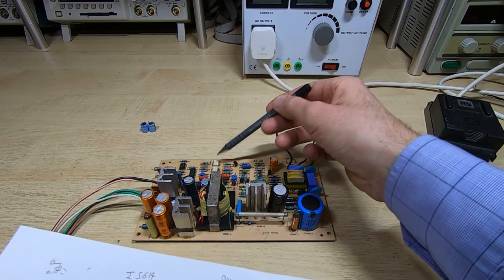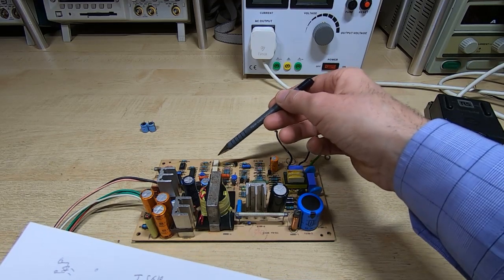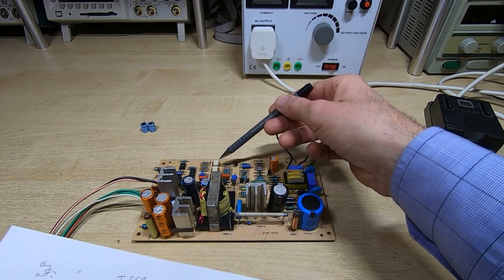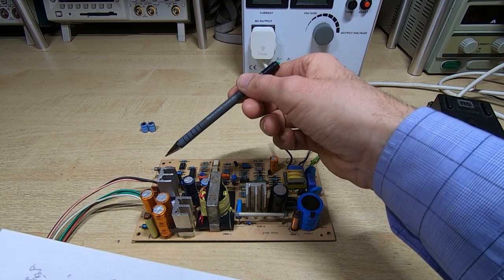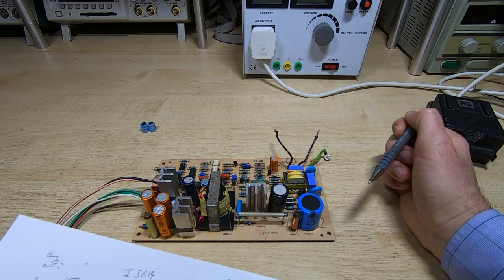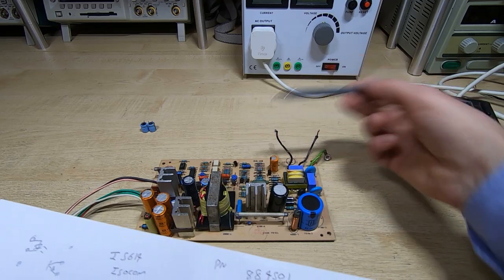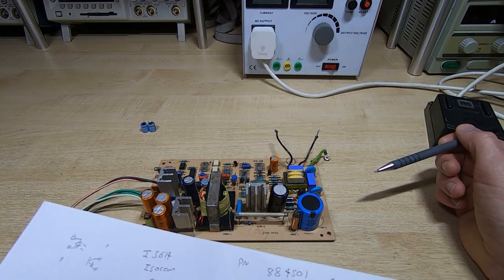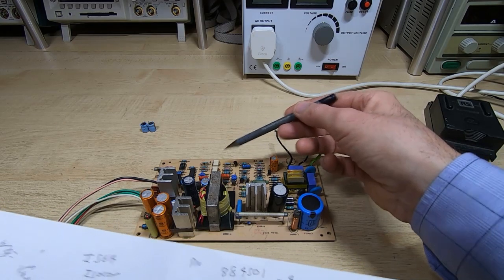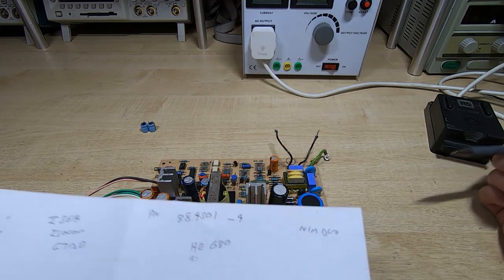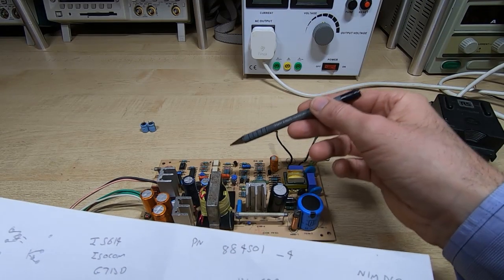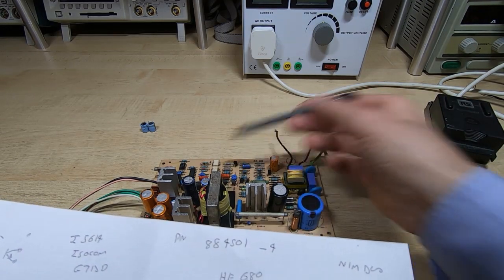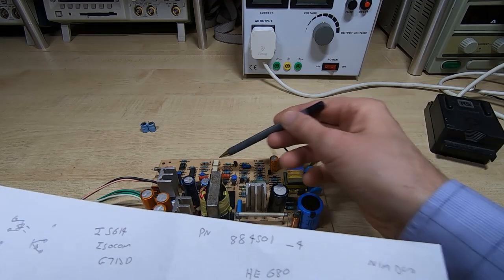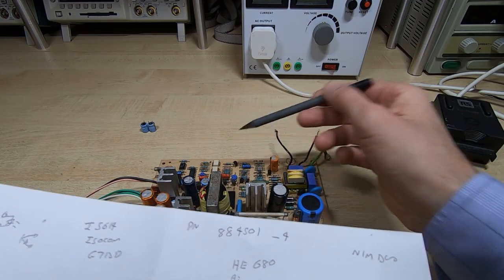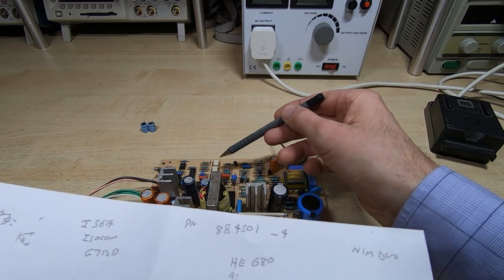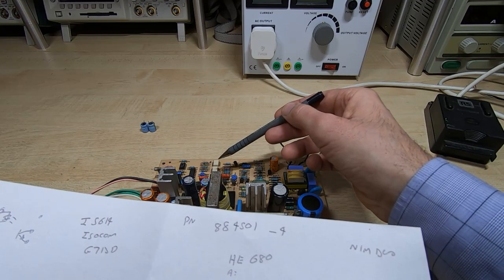You can resolve it down to the output of the optocouplers. In this case, I monitored the voltage on the optocoupler as I applied voltage to the 5-volt rail, and they appeared to be doing what you'd expect. They were turning on slowly as the voltage on the 5-volt rail was increased, and that's what they're supposed to do. As long as they can turn on and off, chances are they're working fine. Again, it doesn't guarantee anything, but it's a first good step. You can quite easily take these out and test them, but I'm not going to do that at the moment. If I need to later on, I'll take them out, but for now I'm going to assume they're working based on the testing I did previously.